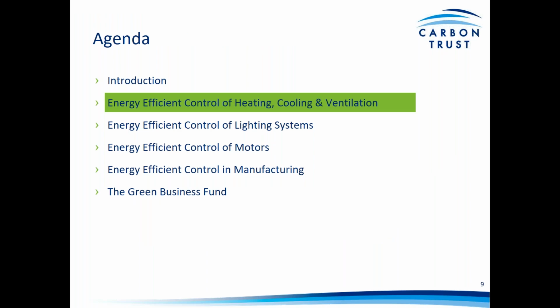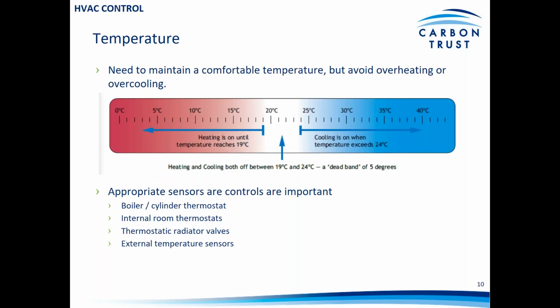So the first area that we'll look at today is the efficient control of heating, cooling and ventilation systems. It's an obvious application of controls, and one of the key areas to focus on is temperature. Obviously there's a need to maintain a comfortable temperature, but you want to avoid overheating or overcooling. As you can see here in the chart, we would recommend the use of a dead band. So we'd recommend that your heating system heats until the building temperature is around 19 degrees Celsius, and we'd recommend that the cooling system cools until the temperature is down to around 24 degrees.